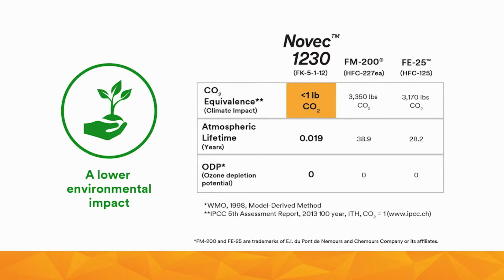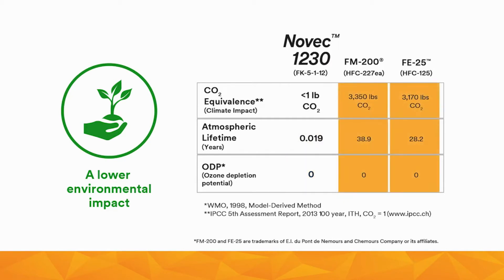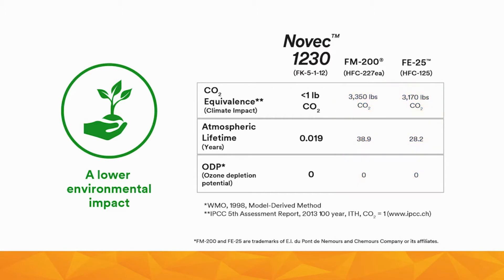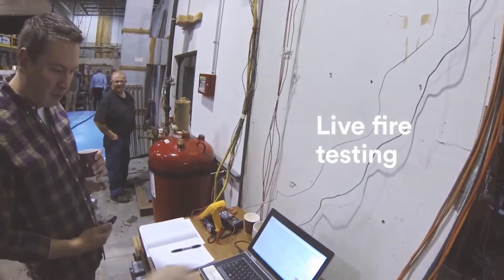Equally important, Novec 1230 fire protection fluid is an environmentally sustainable solution. It offers a global warming potential of less than one, a five-day atmospheric lifetime, and zero ozone depletion potential. Compare these properties to HFCs, which have over 3,000 times the global warming impact of ordinary CO2. This means a lower environmental impact when compared to HFCs, providing a long-term solution for the life of our planet.